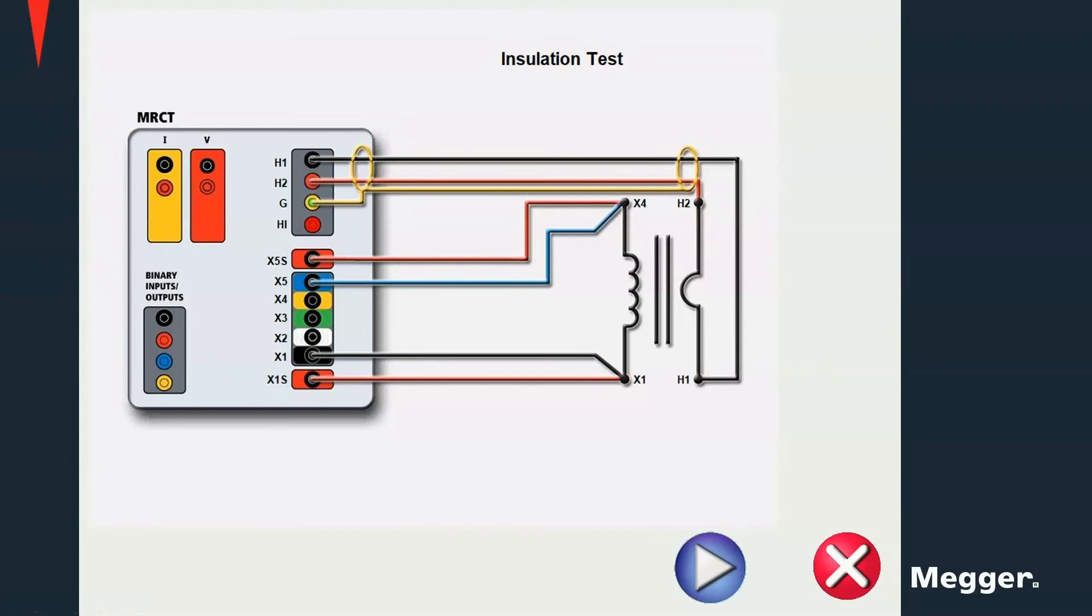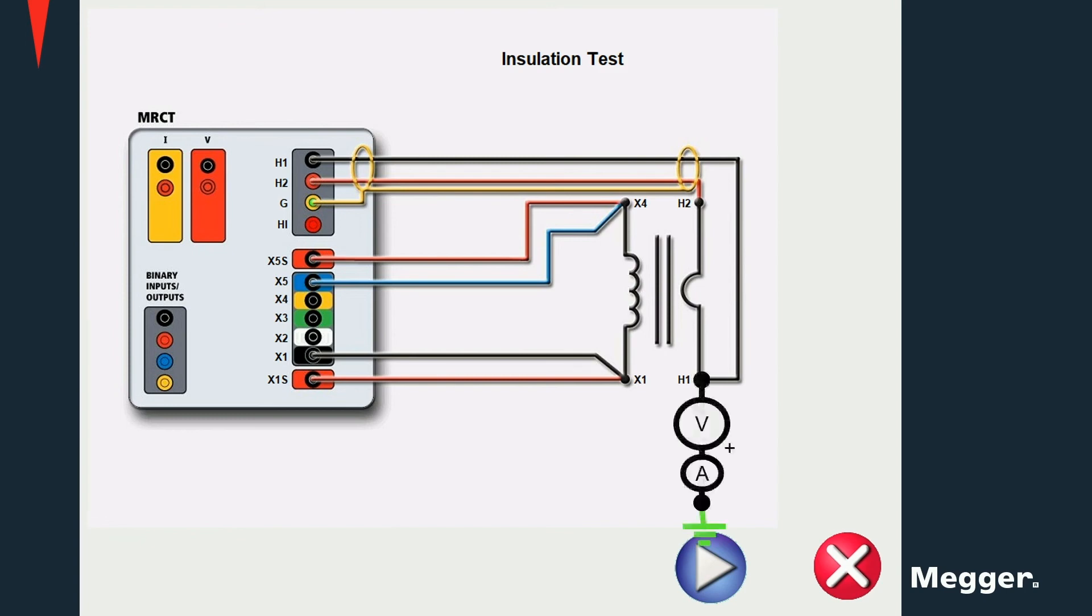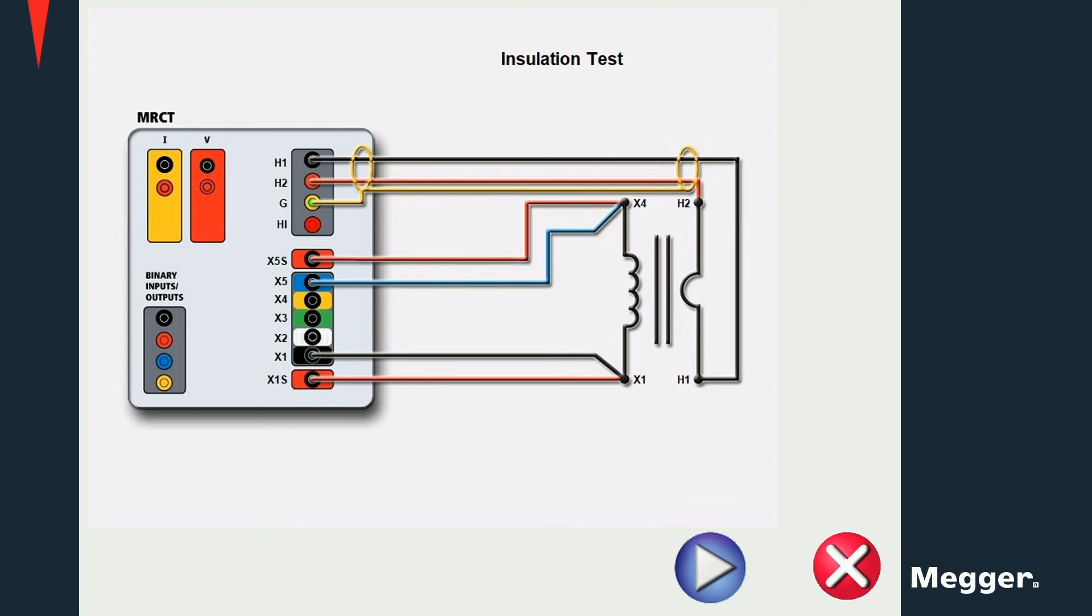For a primary to secondary insulation test, voltage is applied between the primary and the secondary of the CT, and the leakage current is measured. The resistance is then calculated as the ratio between the voltage and the current. For a primary to ground insulation test, a voltage is applied to the primary of the CT, the leakage current is measured, and the resistance is calculated as the ratio of the voltage and the current. For a secondary to ground insulation test, the voltage is applied to the secondary of the CT, the leakage current is measured, and the resistance is calculated using the same method.